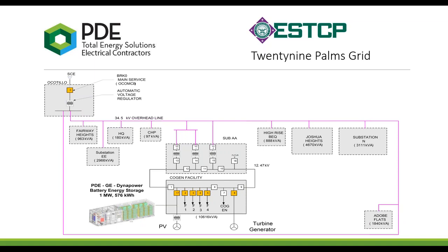Currently when the grid fails, the protective relays 1 and 9 open up and isolate from the grid, and the PV breaker 17 is also tripped off because of the ramp rate constraints of the generator. So our project splices directly into the 1247 PV feeder, and we track the PV production, and the inverter supplements the PV, which is varying, to stay within the ramp rate constraints of the cogen generator. So this is a real project in Southern California.